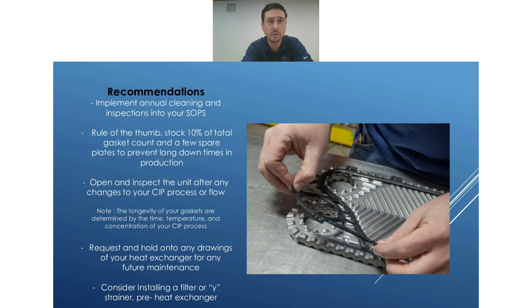We recommend that being annually, or if it's a new heat exchanger, after your first batch and after your CIP process, go ahead and open that heat exchanger up and make sure you're happy with it, make sure you're happy with your cleaning process. That way you're not letting anything hang up in there. That's purely for you, making sure the CIP process is working.